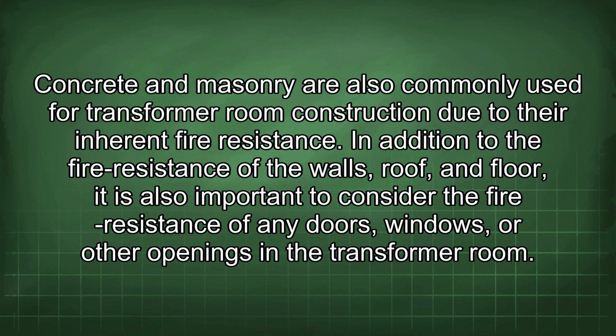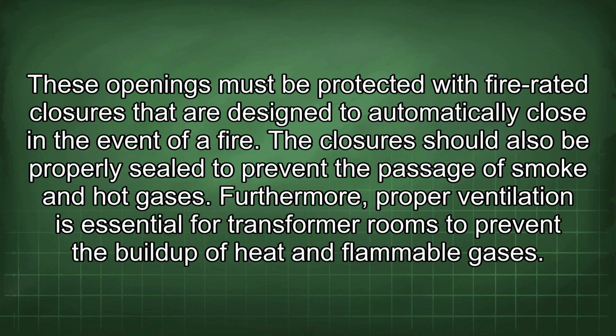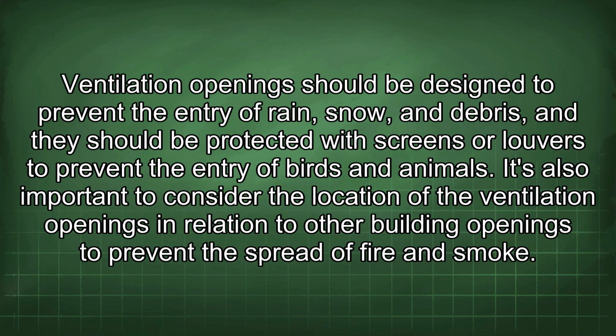In addition to the fire resistance of the walls, roof, and floor, it is also important to consider the fire resistance of any doors, windows, or other openings in the transformer room. These openings must be protected with fire-rated closures that are designed to automatically close in the event of a fire. The closures should also be properly sealed to prevent the passage of smoke and hot gases. Furthermore, proper ventilation is essential for transformer rooms to prevent the buildup of heat and flammable gases. Ventilation openings should be designed to prevent the entry of rain, snow, and debris, and they should be protected with screens or louvers to prevent the entry of birds and animals.